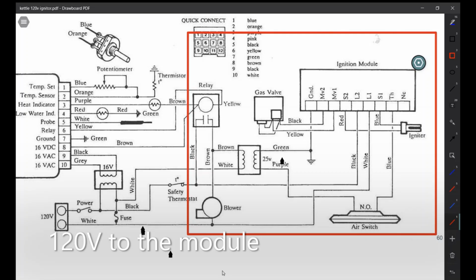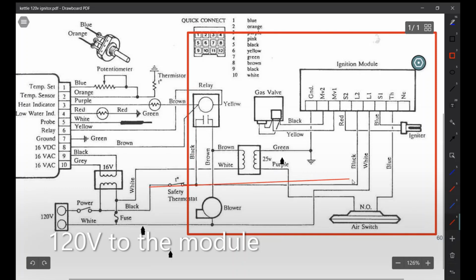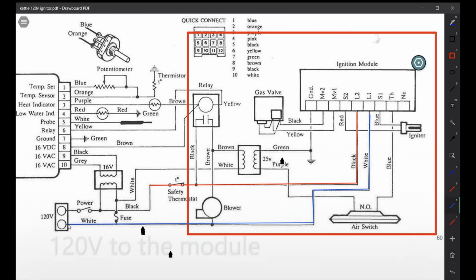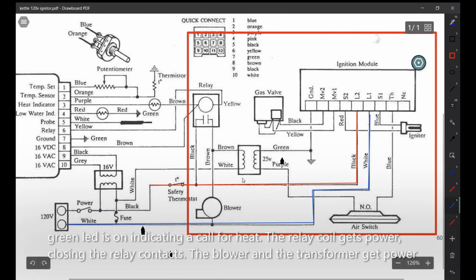Alright, this is for our 120 volt igniter. So we're going to get 120 volts through the high limit onto, they have it here on L2. And then they have the neutral on L1, which is going right back to our incoming power. Okay, the next step now is the green LED will turn on. That indicates a call for heat.